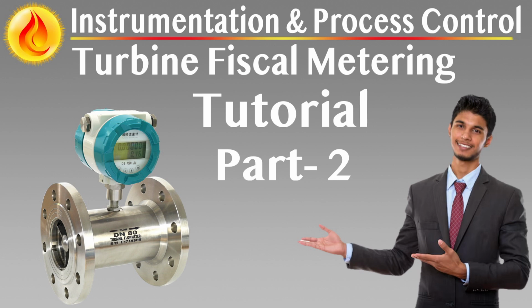Primary and UPS supply design. The system shall be powered from a 400/240 VAC, 50 Hz, 3-phase and neutral supply, as defined by the site standard. In addition to the main supply, an uninterruptible power supply (UPS) must be provided, capable of maintaining system operation for a minimum of 30 minutes. During this window, the metering system must retain volatile memory data, such as integrated totals, configuration parameters, and system states, to avoid data loss and enable seamless recovery.